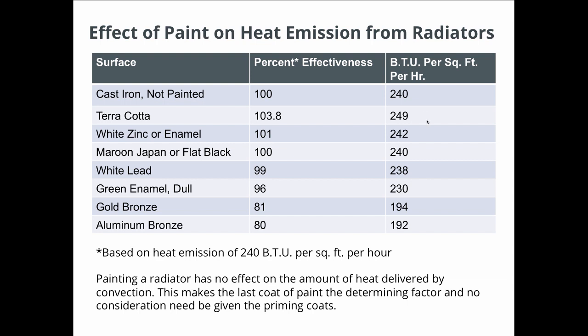So the government finds out that if we use a certain type of paint called a bronzing, an aluminum bronze or a gold bronze paint, this is paint that has metallic flakes in it. If you put that on a radiator as the last coat, it will cut down on the radiator's output by 20%. You see aluminum bronze right here.